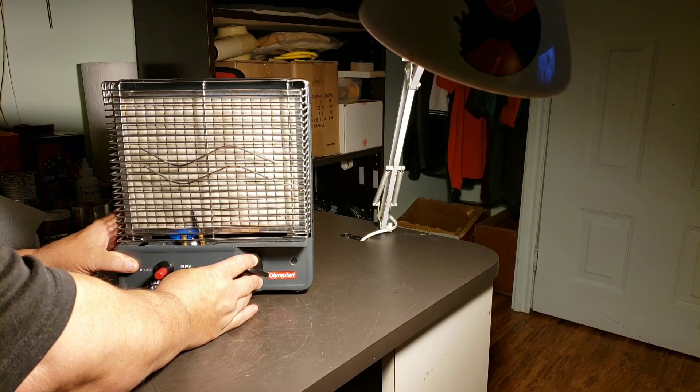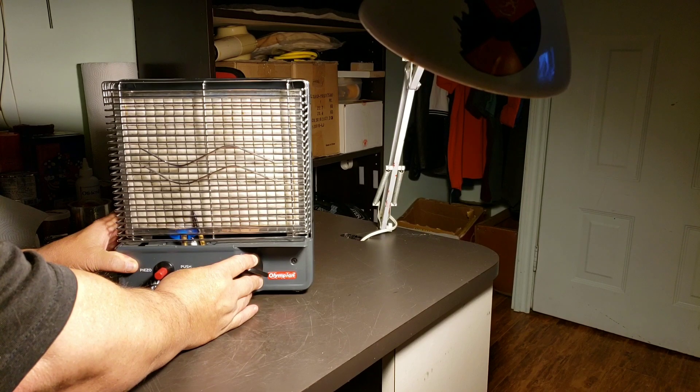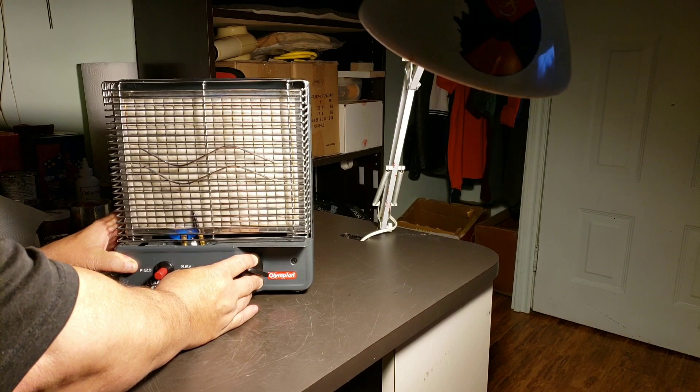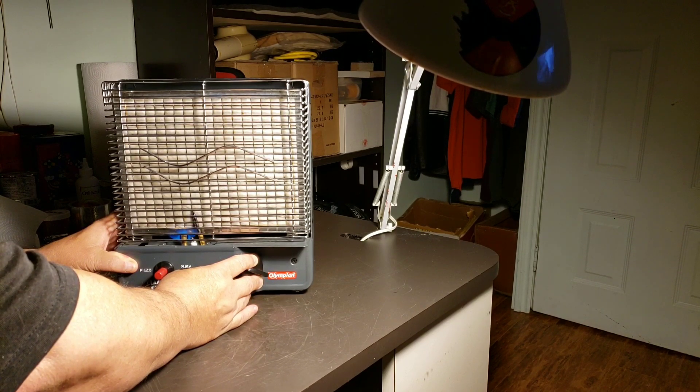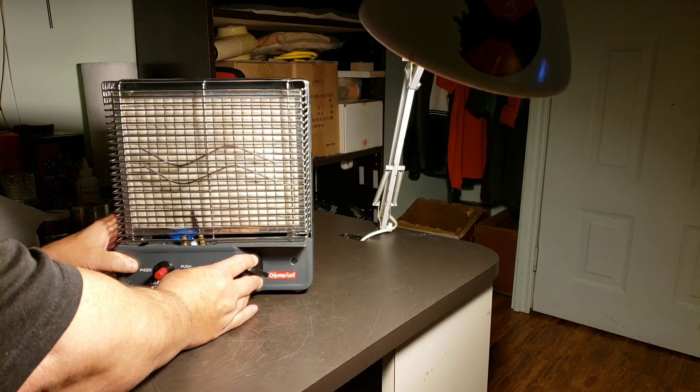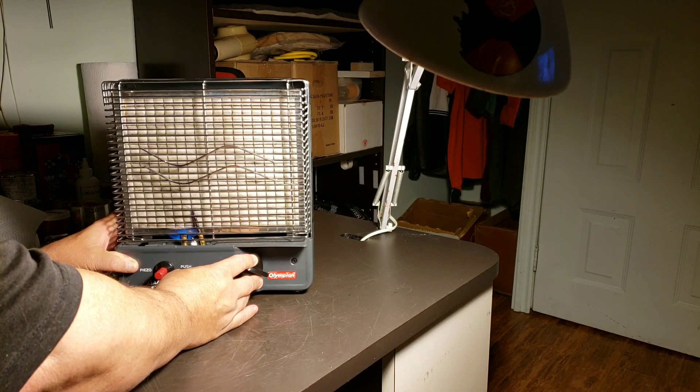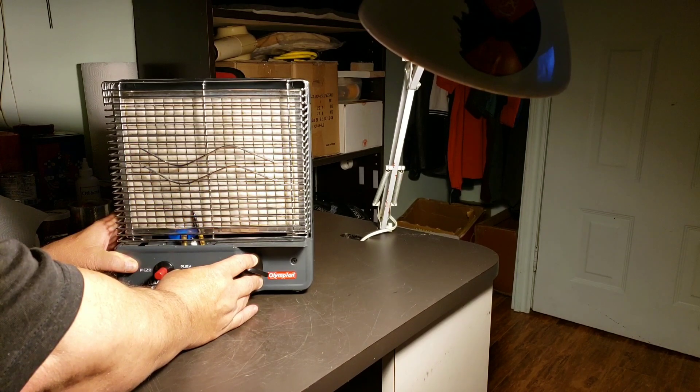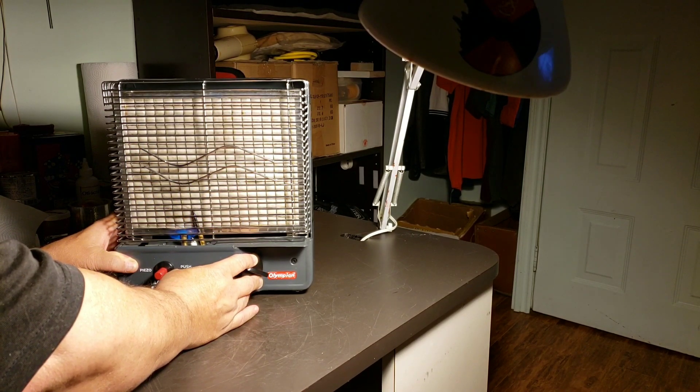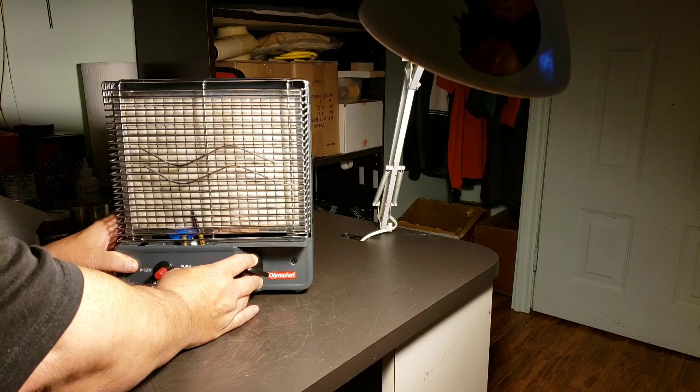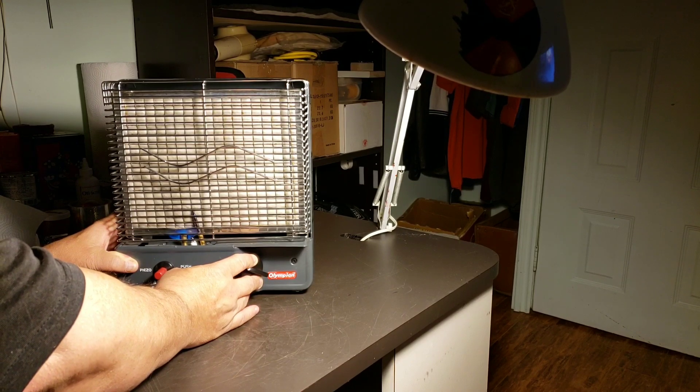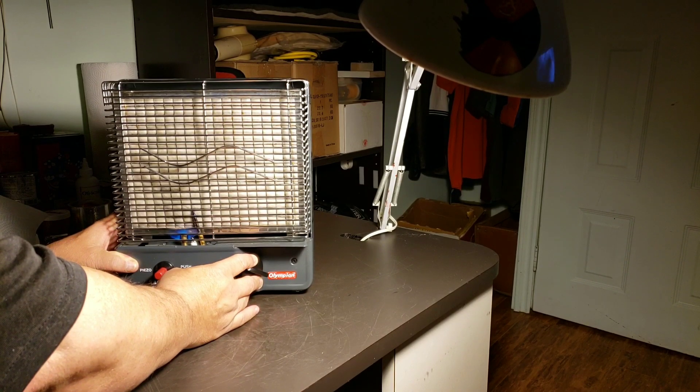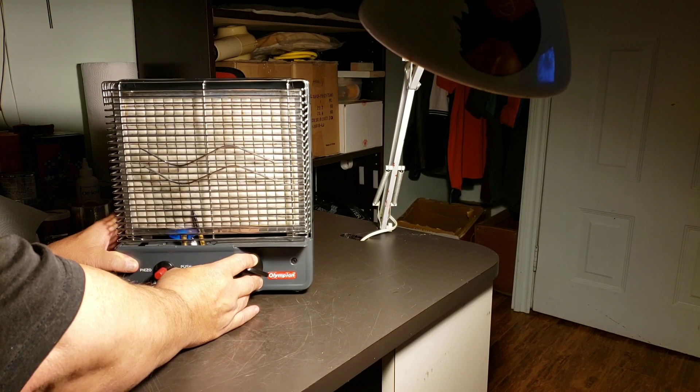So now we just hold it in for about 30 seconds, and then what we're going to do is let go of the black button and then we'll turn it to high immediately. And one way I know that the pad is getting propane is you see it go 'poof' - I don't know if you saw that, but if you watch closely the pad will poof just a little bit across the pad flame once you get a hot spot on the pad.